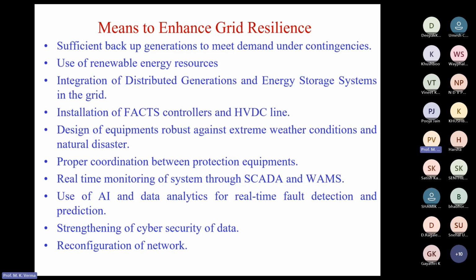You can have renewable energy resources installed at critical locations, distributed generation, and energy storage systems that can be used in the hour of need. You can have FACTS controllers and HVDC lines. The FACTS controller can quickly control the power flow through the lines, and we can put it in critical locations, in critical lines and critical buses, so that if some failure occurs, it can control the system and the system can be recovered.